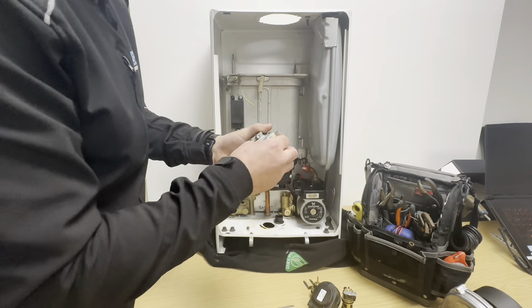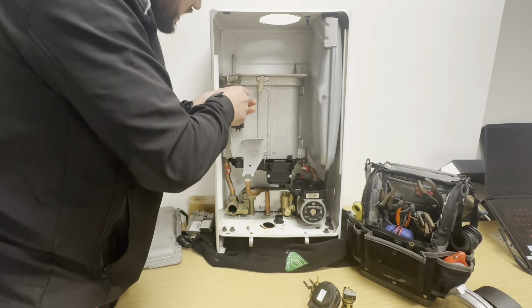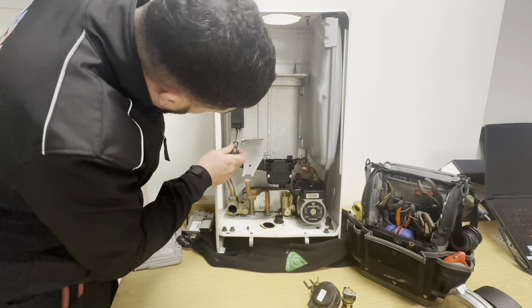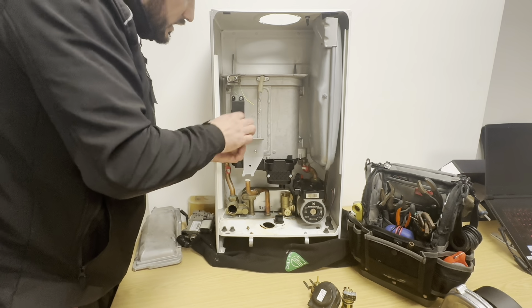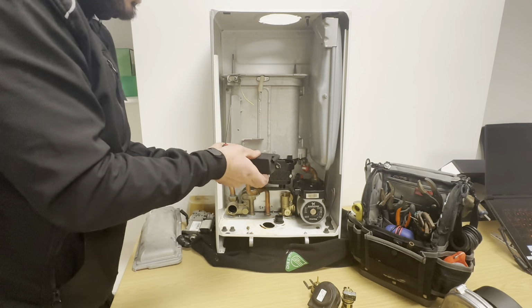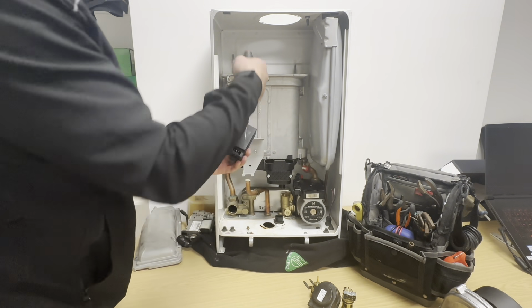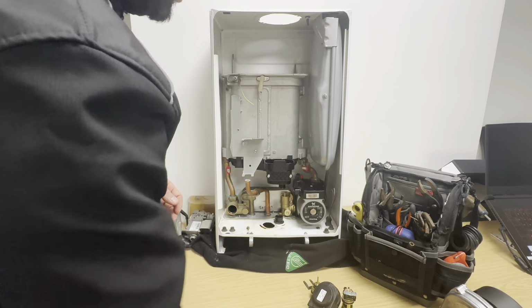So gas valve out now, I don't need the gas valve, I'm not going to bother using that. Connor needs this potentially tonight, he's got a boiler breakdown to go to. So you've got an L2 fault code on an Ideal Logic for a reference of this. L2 comes up as an ignition problem, so that's what I'm going to give him to change tonight. Nine times out of ten, it's your ignition box, which creates a spark inside. So Connor can have that one.